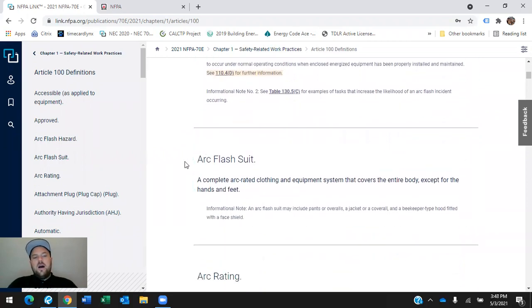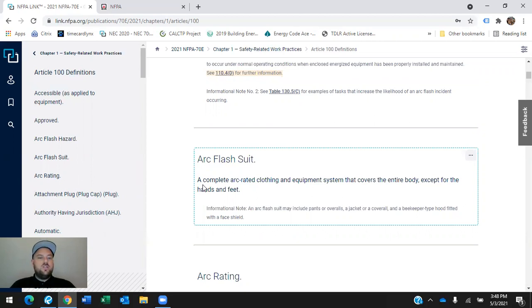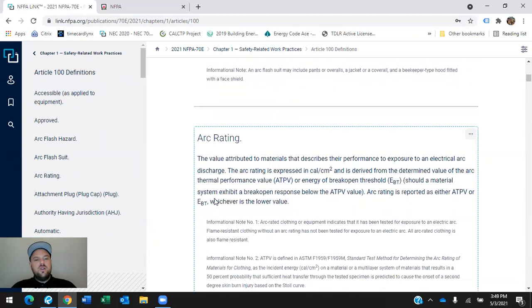Arc flash suit. I don't know how many of you guys have used one of these. Certain arc flash suits have different ratings depending on the voltage that you're using. A 120/208 system has a different rated suit than a 277/480 system, and higher, 12 kV, all those things. We have to make sure that when we are working on energized equipment, which should be a minimum, that we do that. Don't be lazy, find a breaker, shut it off. But in certain circumstances, we're working in live facilities, we're working in a scientific laboratory where they have live experiments going on, and they can't shut the power off to any of this stuff. They have to work hot with the system energized. We have to then take the safety measures and make sure that we follow the proper steps to be safe in that situation.